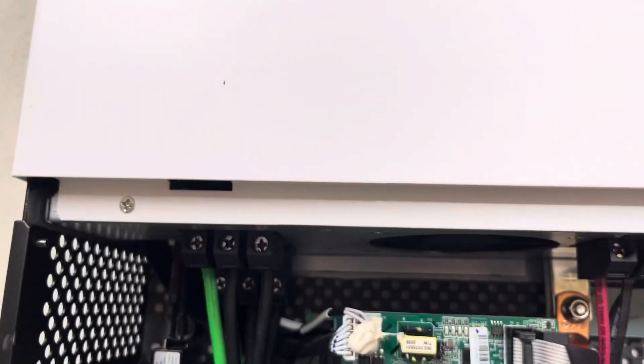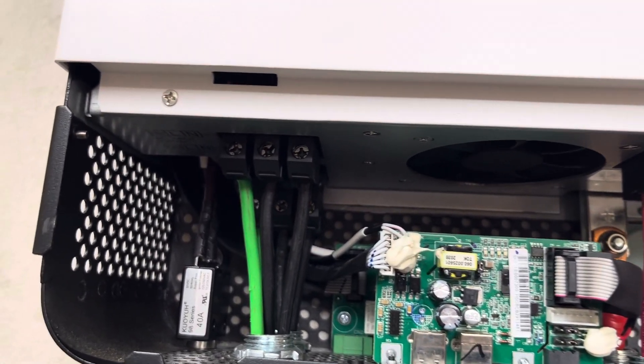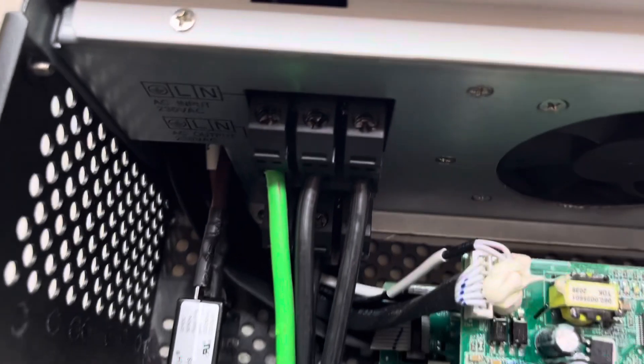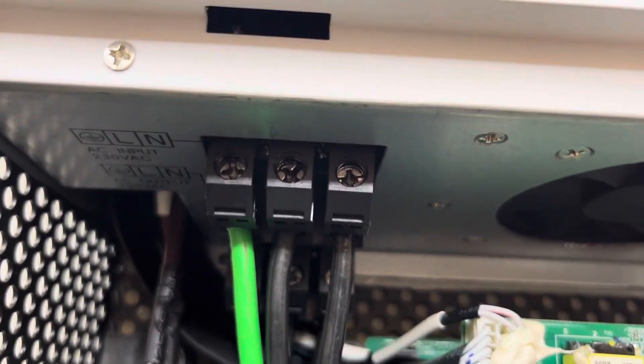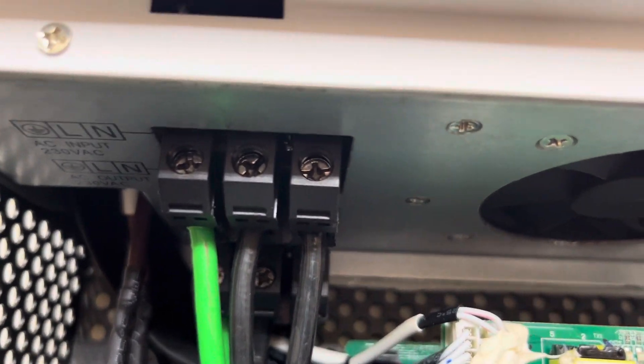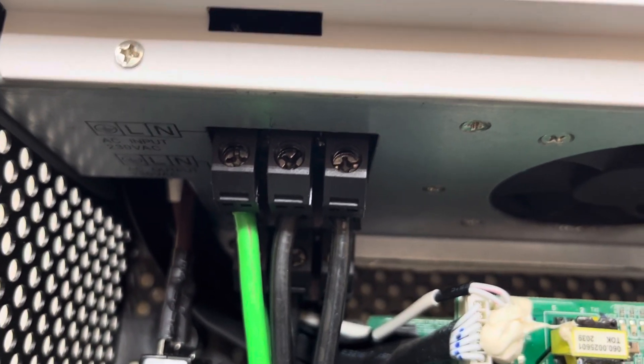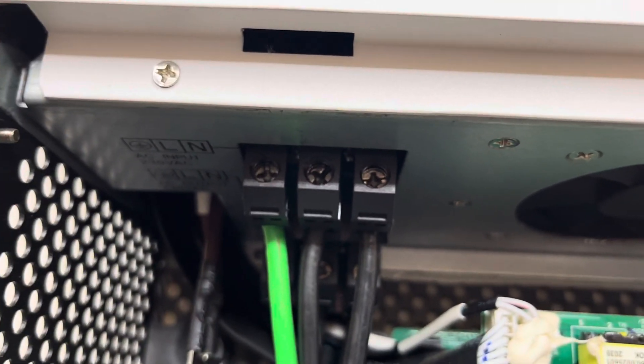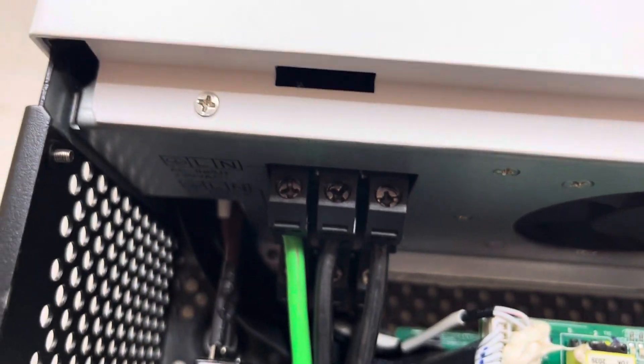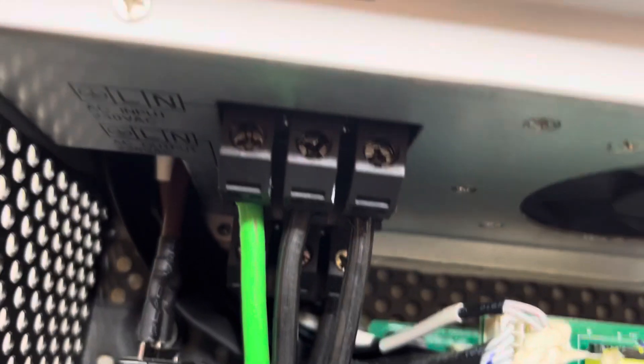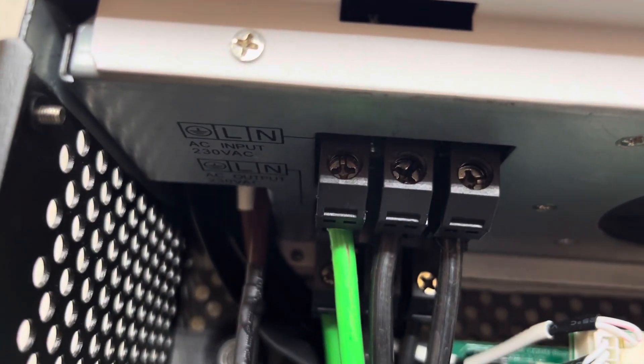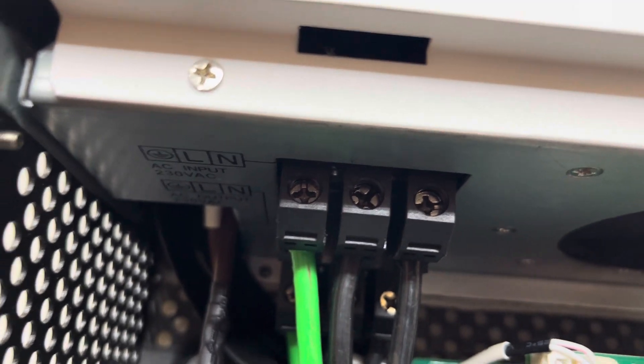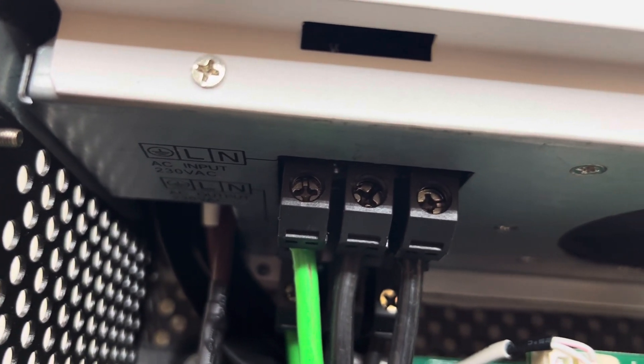But they have adapted this inverter for the American market by removing the bonding screw between N and the ground. So inside this panel, N is not tied to the ground. It's strictly, in our nomenclature, we would call that L1, L2, and then on the far left would be our ground.